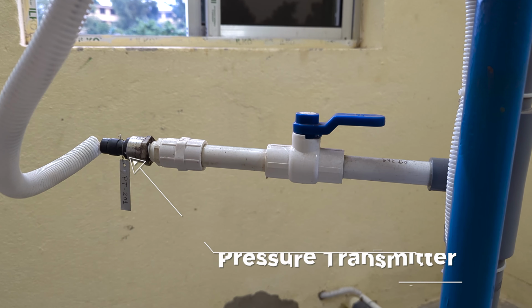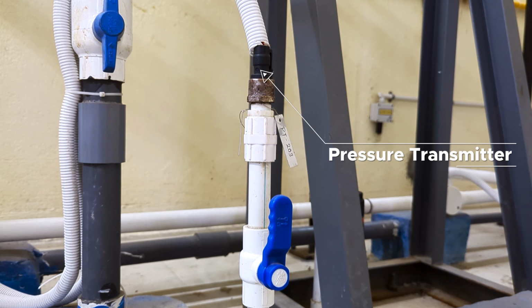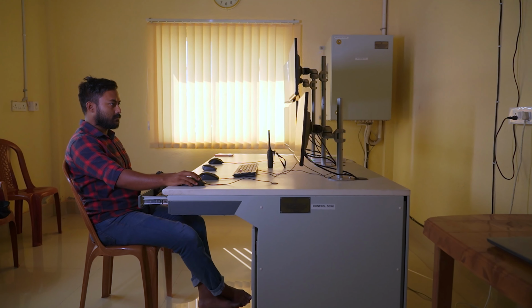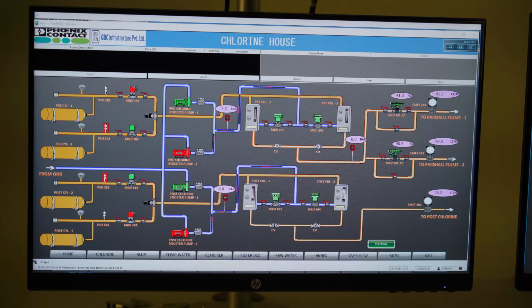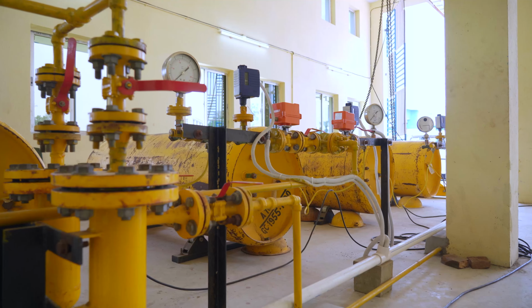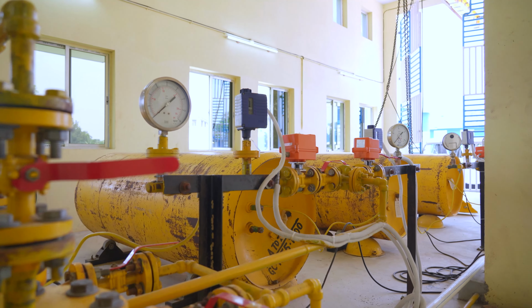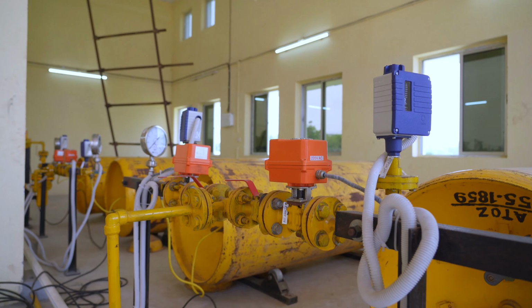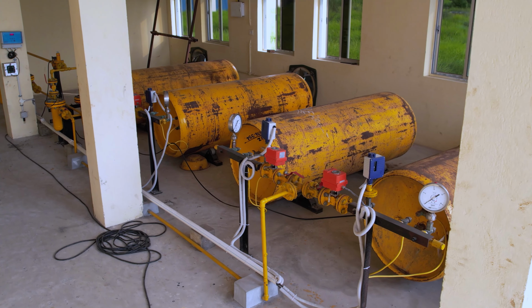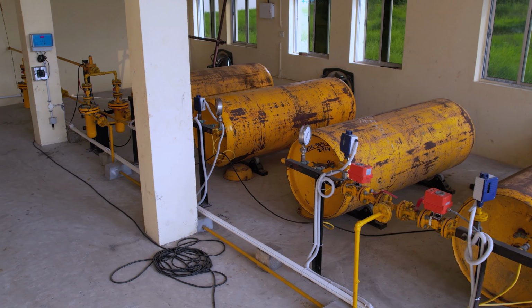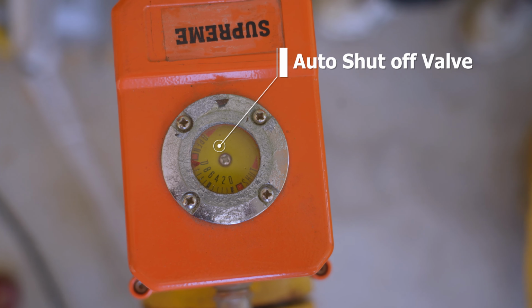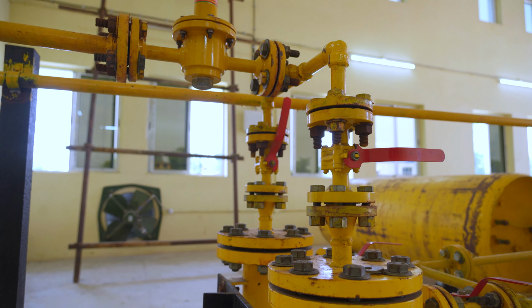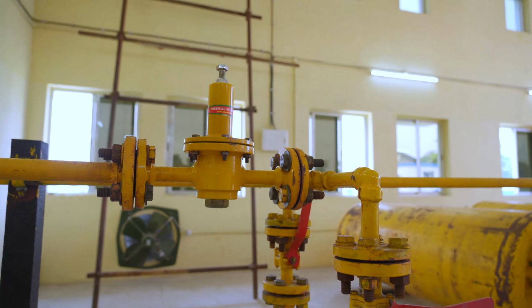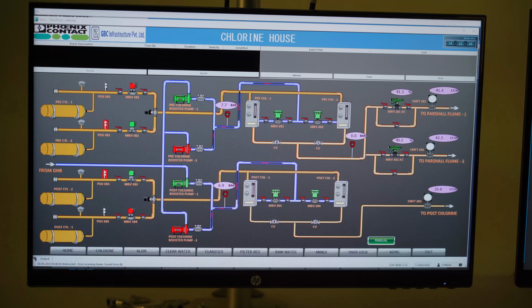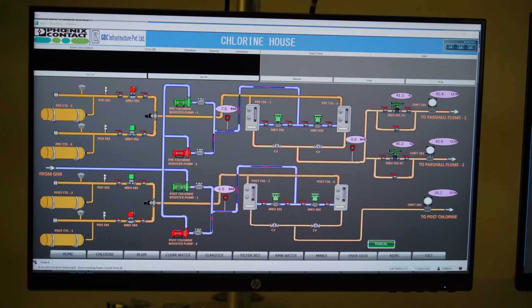There are pressure transmitters fitted on the water line on both pre- and post-chlorination of booster pumps. Signals from these two are used for safety and interlocking. There are 5 chlorine gas cylinders in the toner room, 1 pair each for pre- and post-chlorination and 1 kept as a stock. The toners are connected to gas line through auto shut-off valve, which are interlocked with pressure transmitter and low pressure switch. The valve will only open when the pressure in the water line is above 8 bar and toner pressure is above 1 bar.